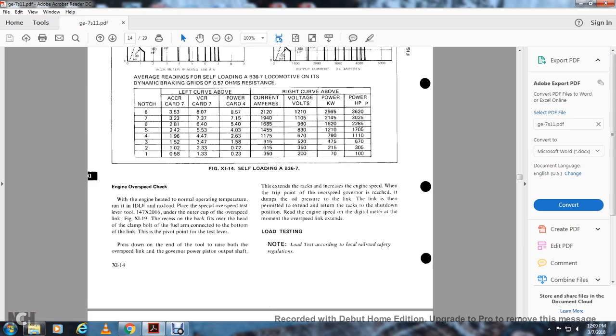Press down on the end of the tool to raise the bolt with the overspeed link, with the governor power piston out to push the shaft with the stand and rack. Increase the engine speed to the trip point of the overspeed governor, which dumps the oil pressure into the link. The link is then permitted to extend and return the racks to the shutdown position. Read the engine speed on the digital meter at the moment the overspeed link extends. Load testing.